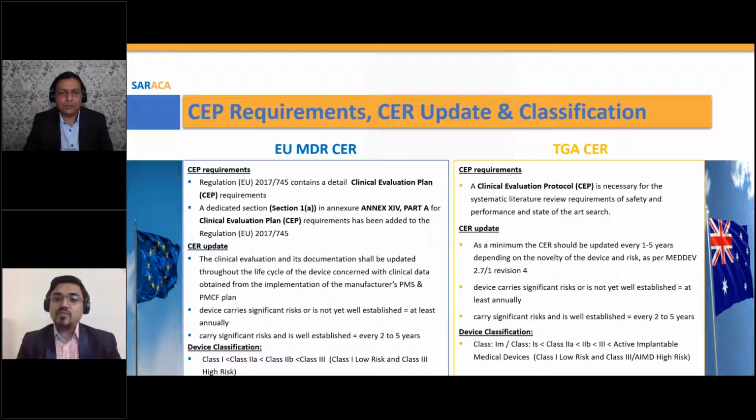In a clinical evaluation protocol, you need to have only the process and requirements which define how you are going to do the literature review, how you are going to appraise those articles, and how you can do the analysis of those articles. Those requirements need to be in the clinical evaluation protocol developed for the TGA CER. But when you come to MDR, you need to have a proper clinical evaluation plan.